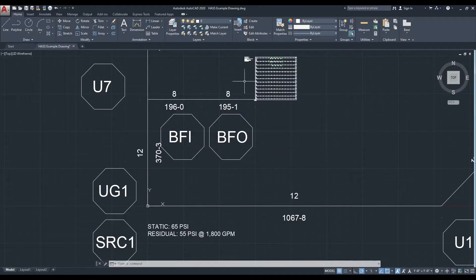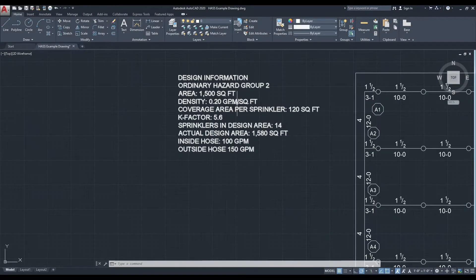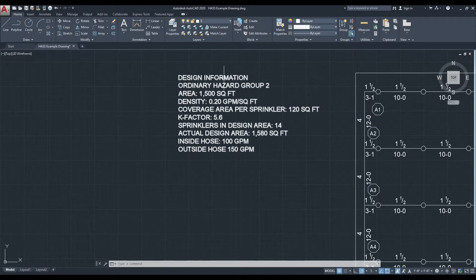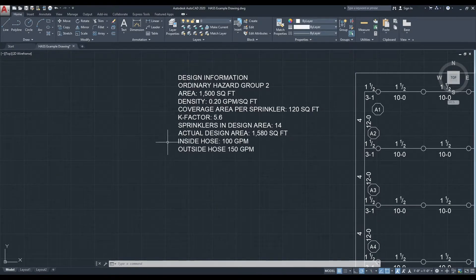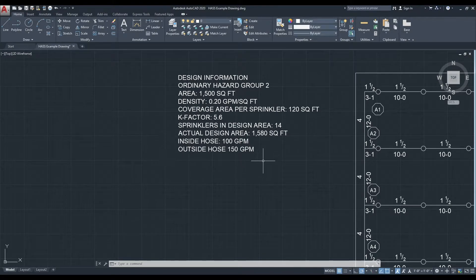Then we need to enter our hose allowance. For this project, we will be using an Ordinary Hazard Group 2 occupancy. That gives us a hose allowance of 250.